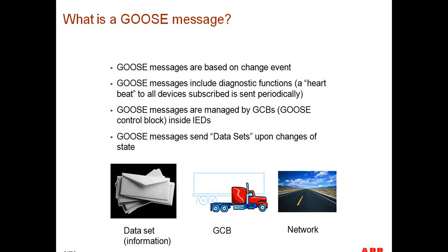The second attribute of Goose messages is that they include a diagnostic function, or heartbeat, sent periodically to all subscribed devices. Goose messages are managed by Goose control blocks inside the relay, and these Goose control blocks are documented as part of your substation configuration language. So you can see the Goose control block, and there are some addressing attributes that are important that we will see in a few slides.